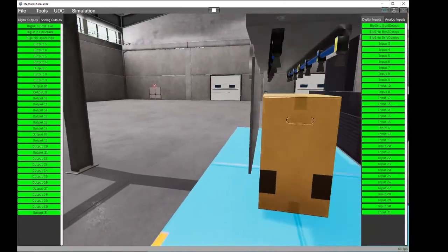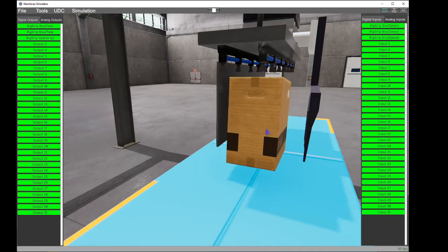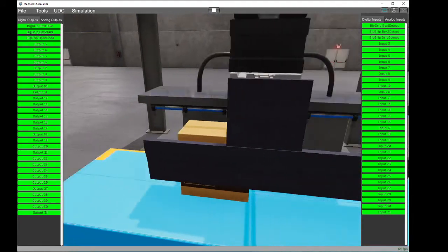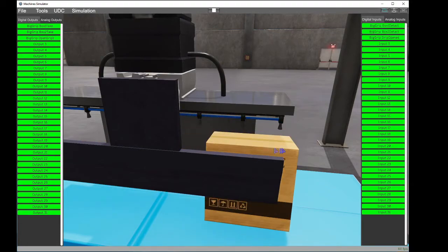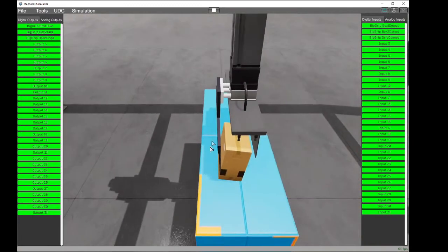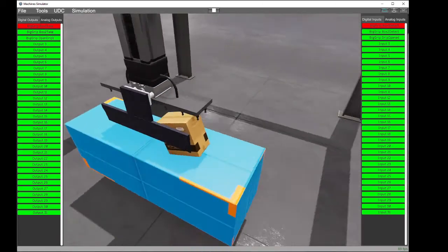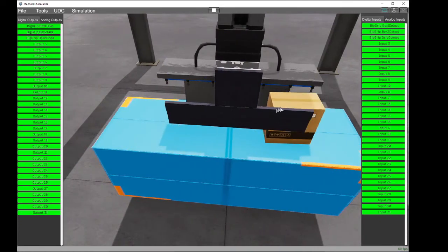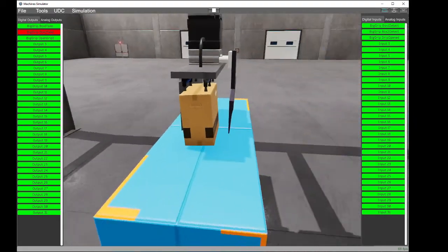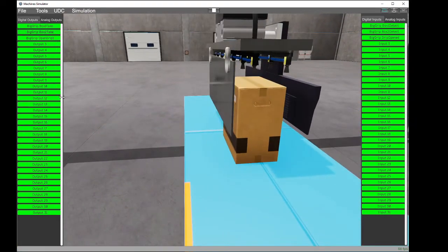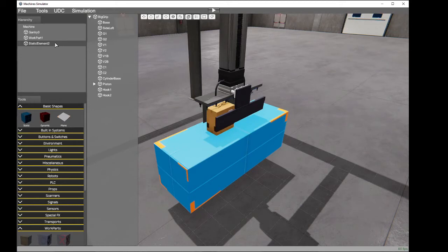Now let's start the simulation. Now, if I take the box, I press the control. Okay, we can verify how when the hook system detects, it will activate the PLC input, and for the other, okay, the same. When the box is detected, the PLC input is activated. If I activate the PLC output to take the parts, we can verify how the box is catched, is hooked, and the same for the two. Okay, when it's taken, it is caged and is released. Okay, we have verified that the logic works okay.